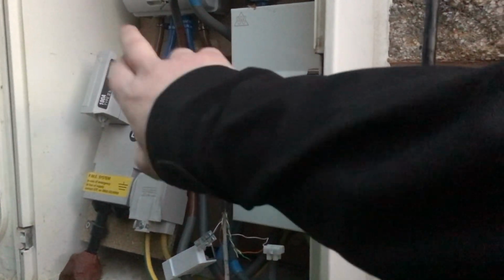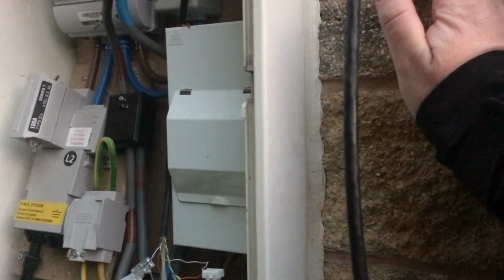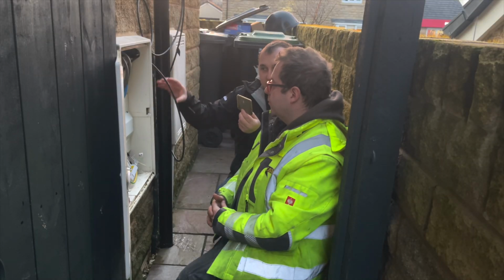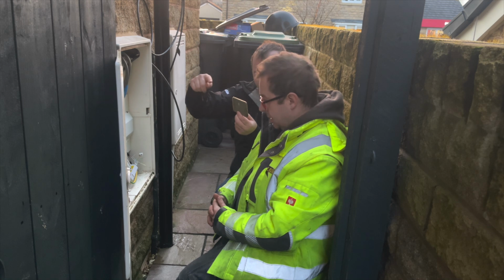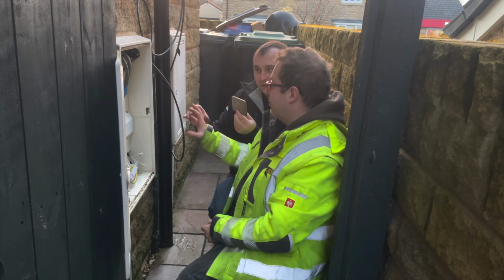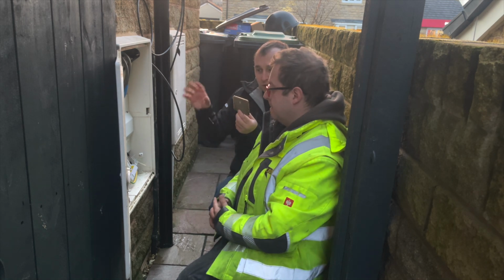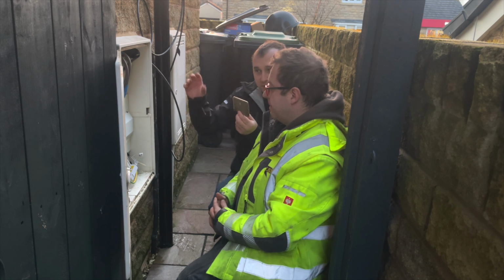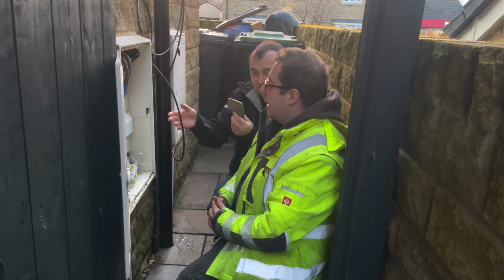So I presume we're ripping this out. Yep, the CTs that go to the house and the garage are going to go in a separate box over here, which will have the meter that talks to the battery inverter. That's right, and it's going to be a separate weatherproof consumer unit. Pretty much all the batteries are very similar in this design, with CT clamps talking back to the battery via a Cat 5 cable.